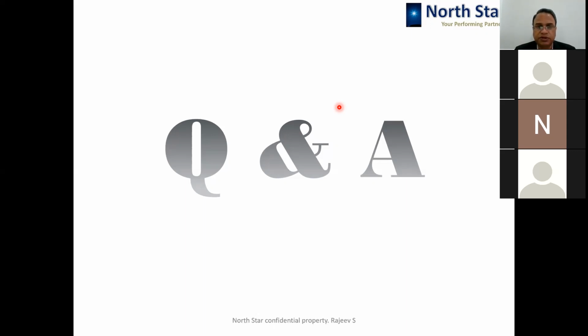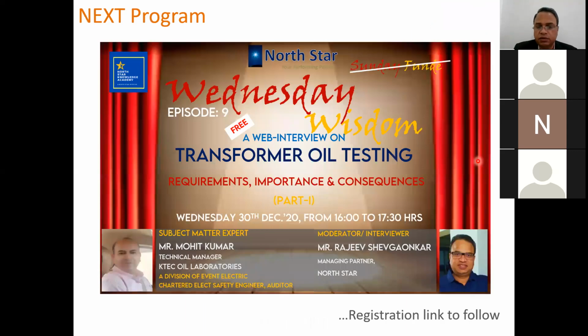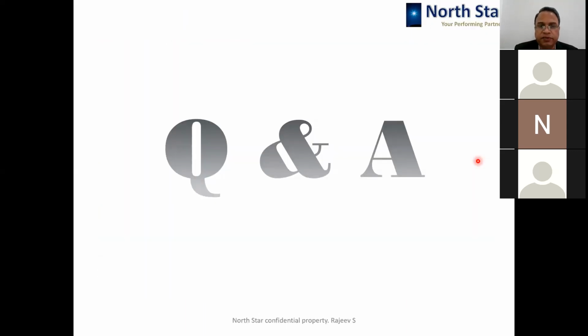Now there's a question from Mr. P. Sharma: what are the site conditions to be considered to design weld joints? In Rajasthan, a 315 MVA, 400/220 kV transformer failed due to a three-phase short circuit at the 220 kV side. The three-phase fault was cleared at 59 milliseconds, but the transformer failed. As per analysis, one-phase winding was damaged, OLTC was damaged, and the tank of the transformer burst from the bottom. Is it technically feasible to repair this transformer?